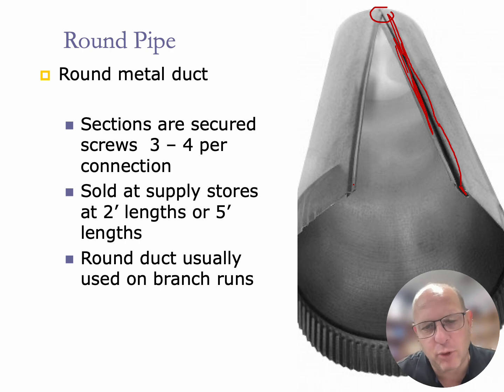Now, the screws that we're going to put into this ductwork, I say 3 to 4. So you're going to put a screw there, you're going to put a screw there, and you're going to put a screw in there. And this is going to hold that metal pipe or that round pipe from moving in any direction that we have on that particular branch. Okay, so we're going to put that together in that Pittsburgh. We almost have to take it and make it into an oval shape for that pipe to slip into the Pittsburgh of the metal pipe as we're running it.